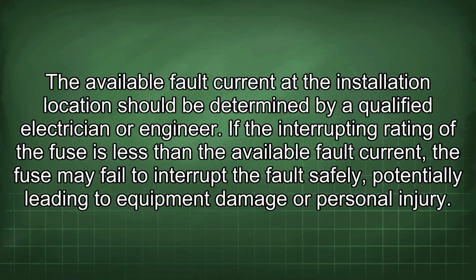The available fault current at the installation location should be determined by a qualified electrician or engineer. If the interrupting rating of the fuse is less than the available fault current, the fuse may fail to interrupt the fault safely, potentially leading to equipment damage or personal injury.